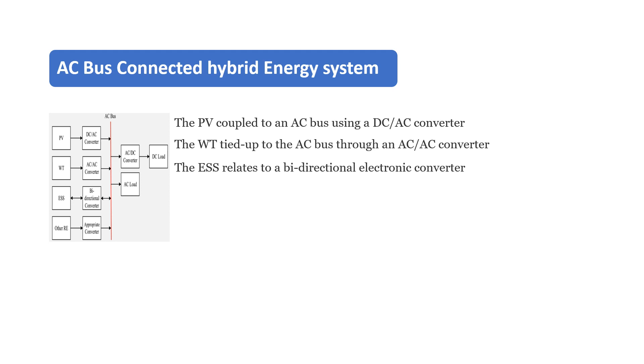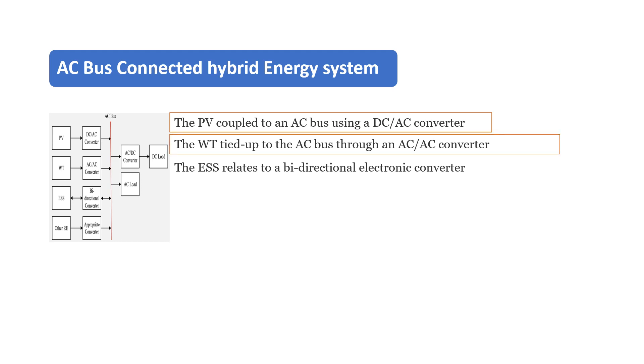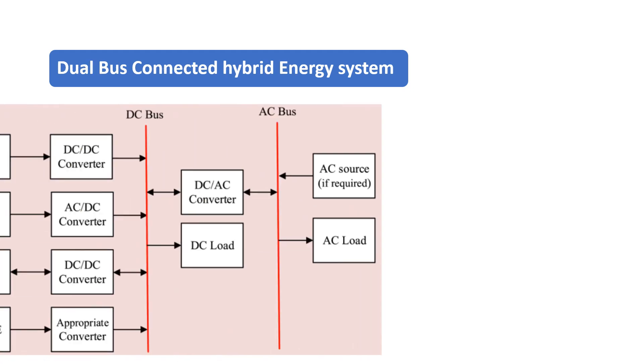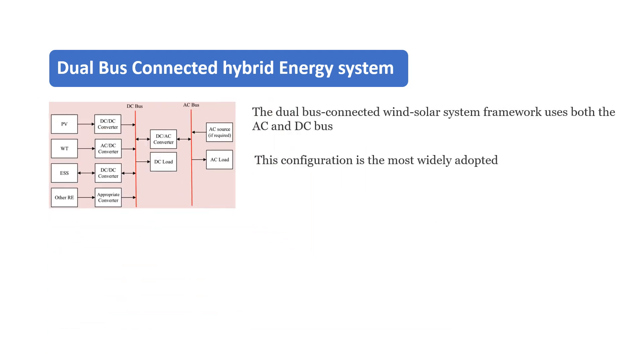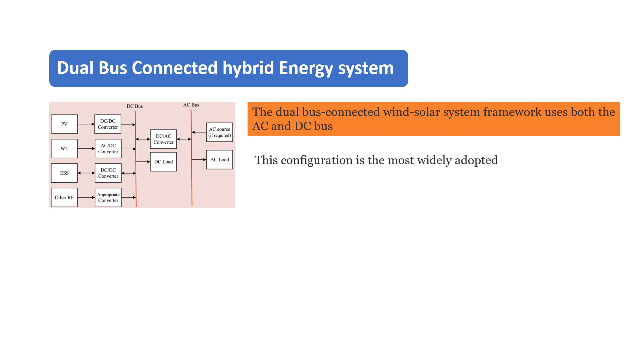In AC bus connected architecture, the PV is coupled to an AC bus using a DC-AC converter, and the wind turbine is tied to the AC bus through an AC-AC converter. The ESS connects via a bi-directional electronic converter. The dual bus connected wind-solar system uses both AC and DC buses, and is the most widely adopted due to its flexibility to combine energy sources and loads irrespectively.